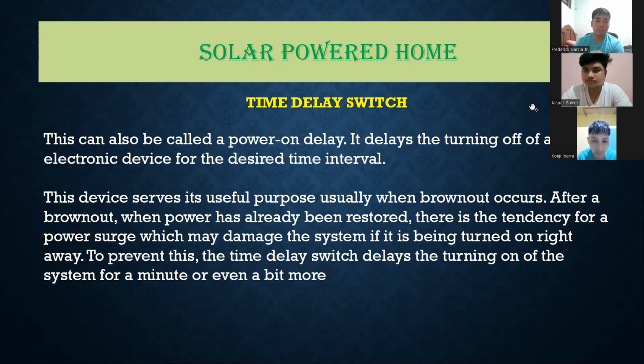So now in the event of a power outage, right? If the power comes back on and all the devices were not turned off, there could be a possibility for a surge since all the devices will be trying to have what we call inrush current all at the same time. This could lead to a surge. The time delay switch prevents that from happening. It delays the power to a certain device or a certain power outlet or a certain circuit by a predetermined amount of time in order to prevent such a surge from happening.